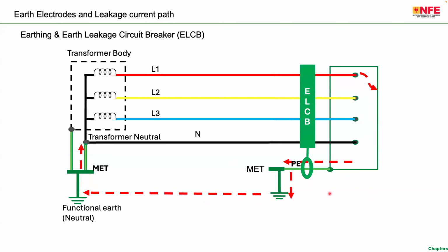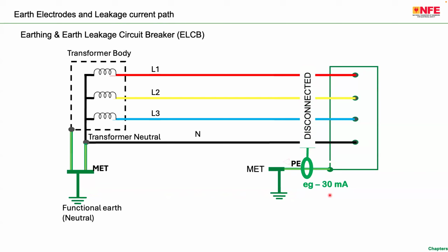That leakage current is measured, and this measurement is connected to a mechanical device. Then there is a set current, let's say for example 30 milliampere. Once the leakage current is more than 30 milliampere, the mechanical device disconnects the supply. As a result, the leakage current or the fault current is also stopped. So basically, the current through the protective earth conductor is measured in an ELCB and the device is disconnected. The measurement of this particular current is very critical in an ELCB. As I already told, current operated ELCBs are no more available in the market, and they are not recommended in the standard.